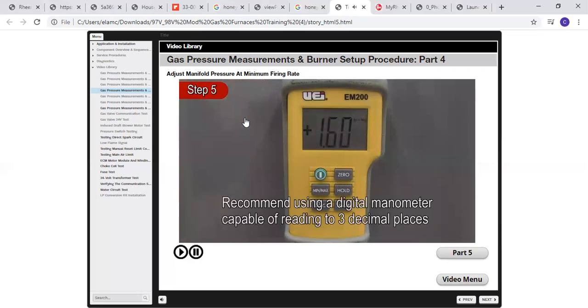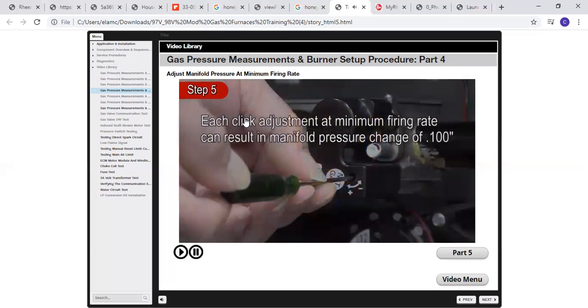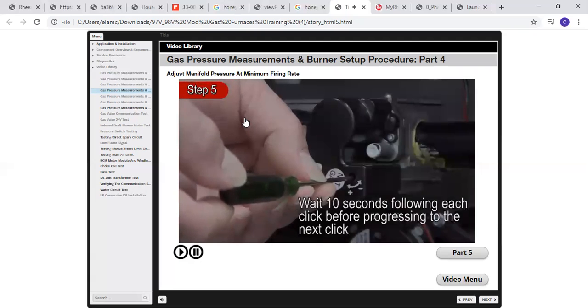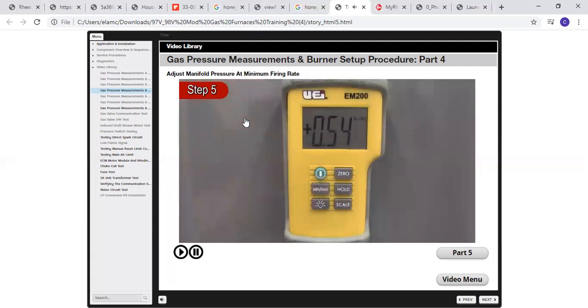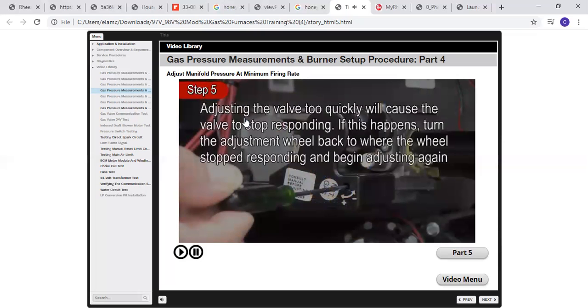Recommend using a digital manometer capable of reading to 3 decimal places. Each click adjustment at minimum firing can result in a manifold pressure change of 0.100. Wait 10 seconds following each click before progressing to the next click. Verify the new manifold pressure following each adjustment. Adjusting the valve too quickly will cause the valve to stop responding.